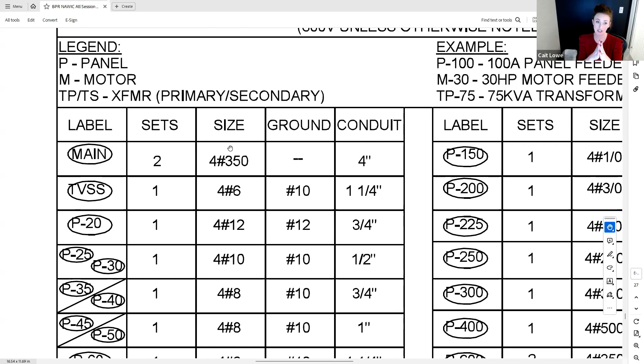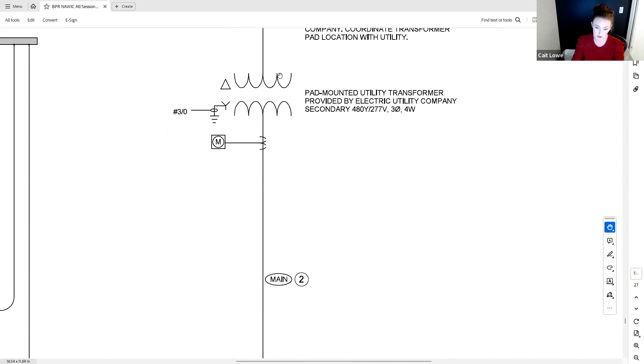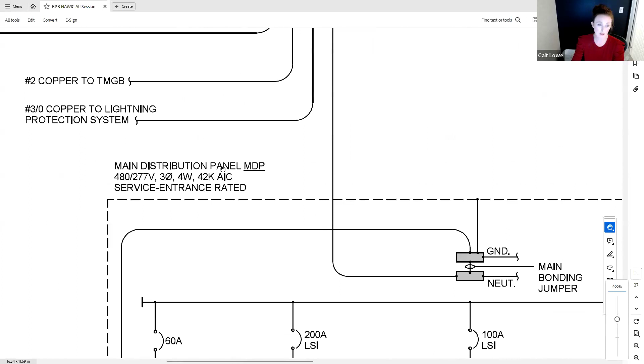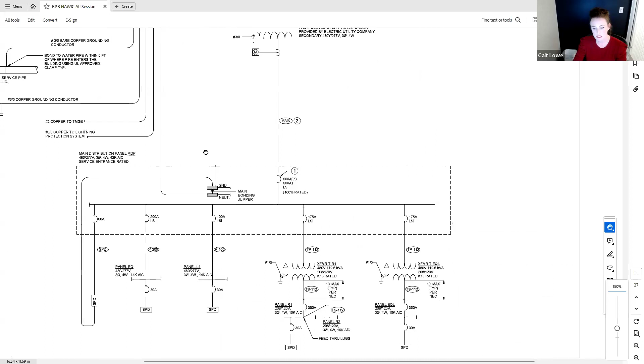4#350 is the wire size, don't worry about it right now, 2 sets, so times 2. So 2 4-inch conduits with 4#350 wire inside, going from - and I'm going to look at the main - going from this utility pad transformer to our main distribution panel, the main gut panel, the big panel that's in there. I'm like, oh okay, it doesn't say if I'm going above ground or below ground. Well, that's where we've got to think about it, and we're going to look at note 2.